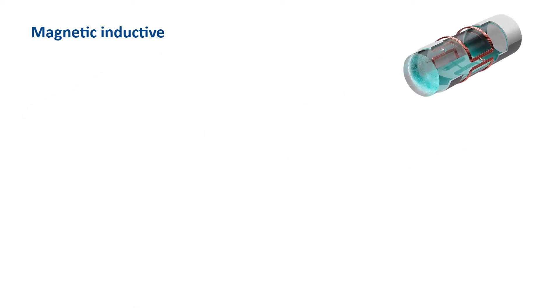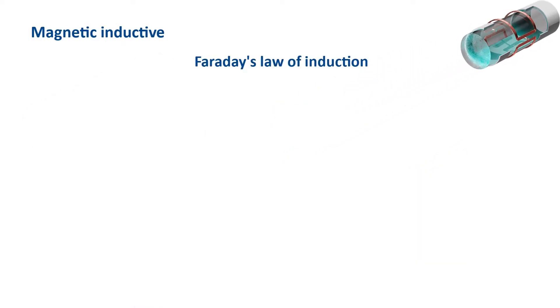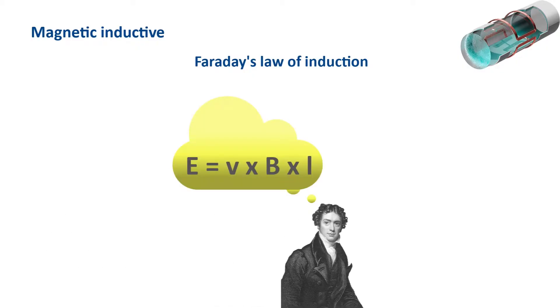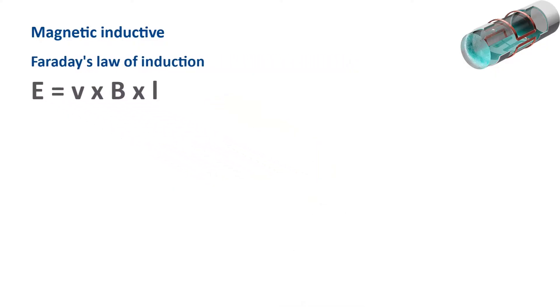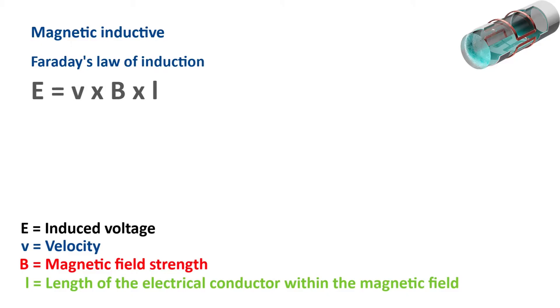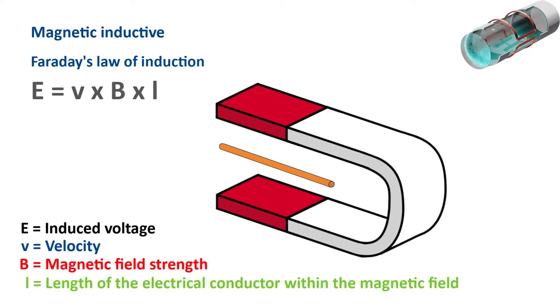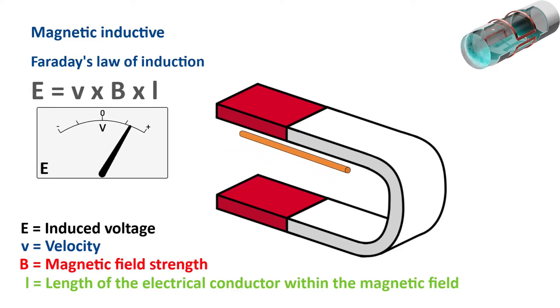The magnetic inductive sensor works according to Faraday's law of induction. This states that when an electrical conductor moves through a magnetic field, a voltage is generated in it. This voltage is proportional to the speed of the electrical conductor in the magnetic field. The induced voltage depends on the length of the electrical conductor, the magnetic field strength, and the speed of the conductor. The polarity of the voltage depends on the direction of movement of the conductor.